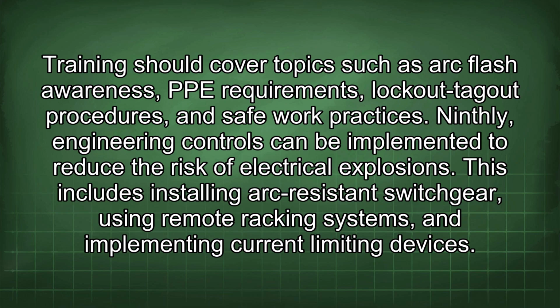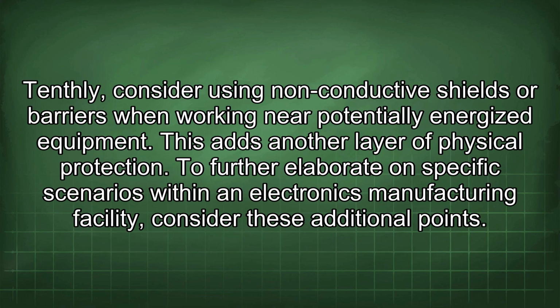Ninthly, engineering controls can be implemented to reduce the risk of electrical explosions. This includes installing arc-resistant switchgear, using remote racking systems, and implementing current-limiting devices. Tenthly, consider using non-conductive shields or barriers when working near potentially energized equipment. This adds another layer of physical protection.